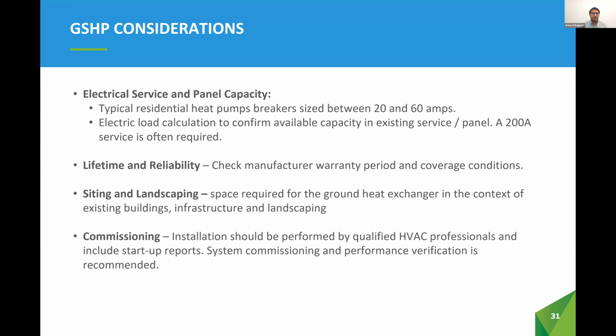Finally, some other considerations. Again, as with ground source, as with air source, the electrical service panel capacity must be considered. The lifetime and reliability, again, manufacturer warranty periods and coverage conditions must be checked before purchasing a unit. But we should also consider siting and landscaping. Actual space is required for the ground heat exchanger in the context of existing buildings, infrastructure, and landscaping.